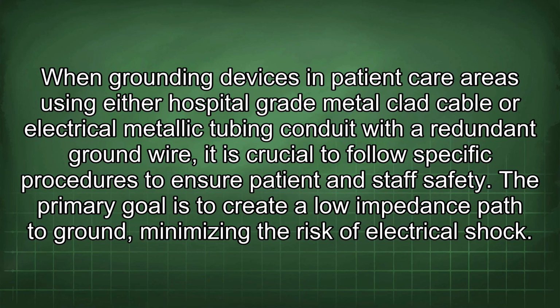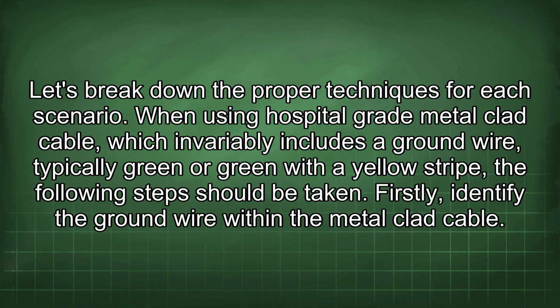When grounding devices in patient care areas using either hospital-grade metal-clad cable or electrical metallic tubing conduit with a redundant ground wire, it is crucial to follow specific procedures to ensure patient and staff safety. The primary goal is to create a low impedance path to ground, minimizing the risk of electrical shock. Let's break down the proper techniques for each scenario.